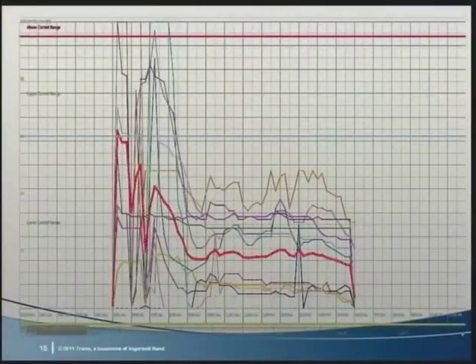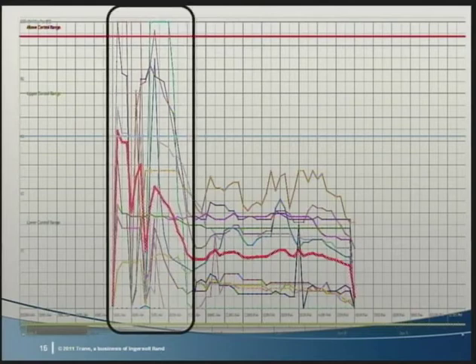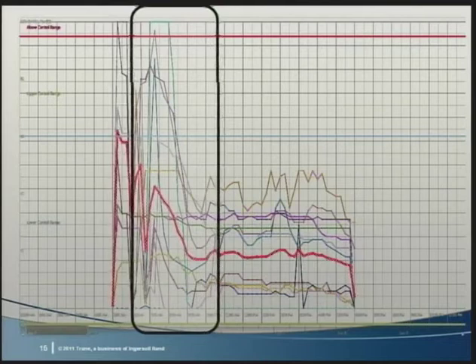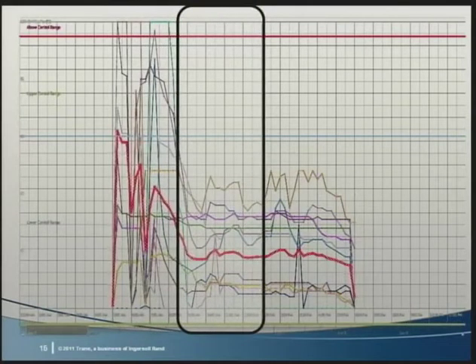Here's an example of an airside control that is available but not activated. Now the bold red line on this chart is the average VAV box position. We can see that on Monday morning, the box is opened at 5 a.m. to bring the zones into the occupied state. But by 9 a.m., no box is more than 50% open, signifying that the duct static pressure was not reduced to save fan energy. In this case, reducing the fan static pressure set point could have saved a significant amount of fan energy.